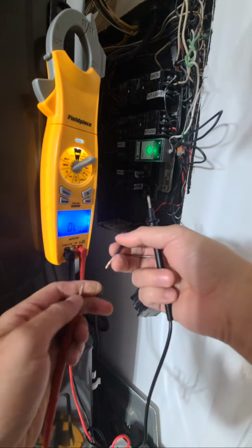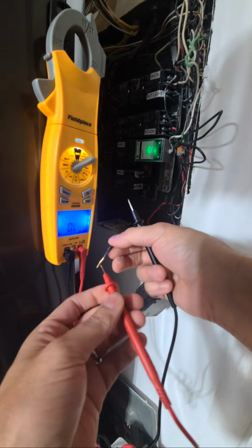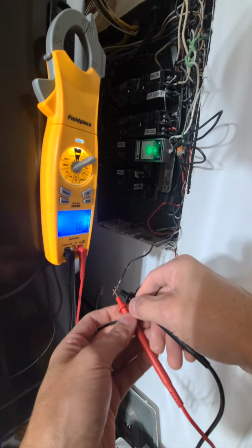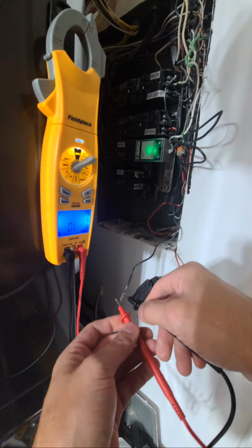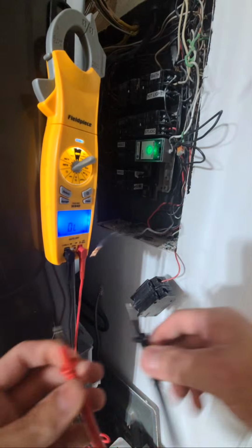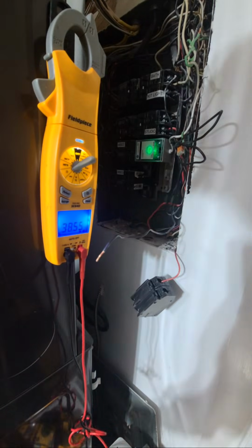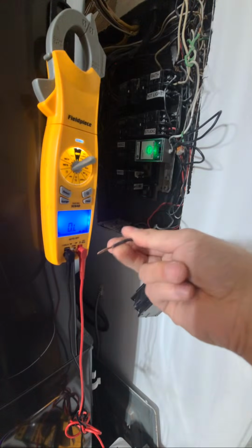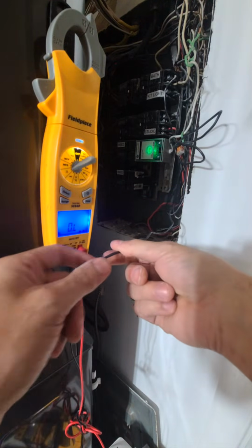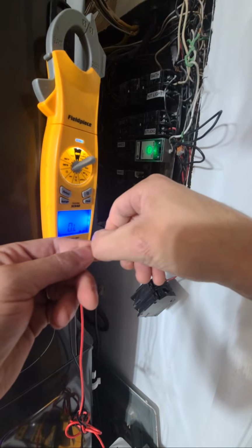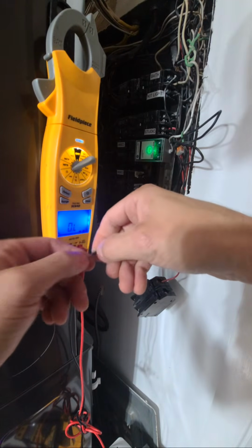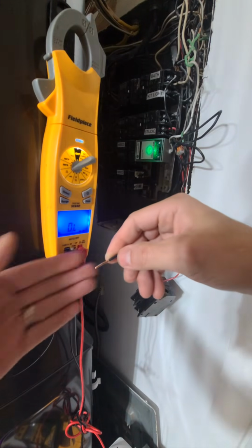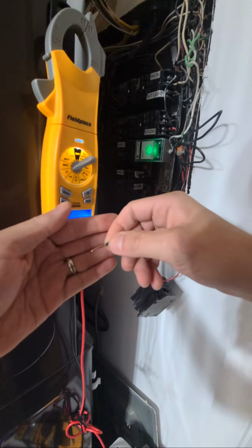Holding steady. And if we go to this damaged part of the copper where we were pitting it, you're going to see here where we're just not going to get 0. You're going to get 1.6, which is a pretty common number. So we've got permanent resistance installed in here. Your best bet as a homeowner, as a technician, is to cut to brand new copper, re-strip, because anytime you have pitting and oxidation like this, that's exactly what that is, oxidation in the copper. And that's why it's that gray color. It'll never be the same.